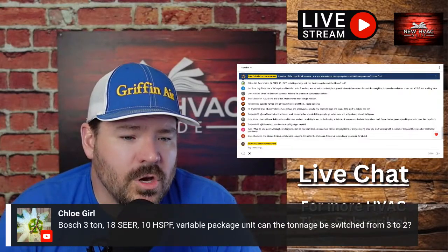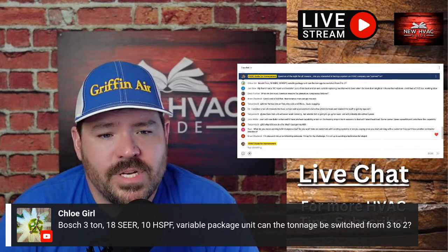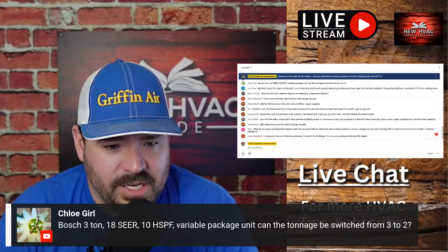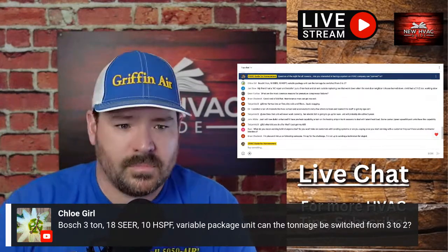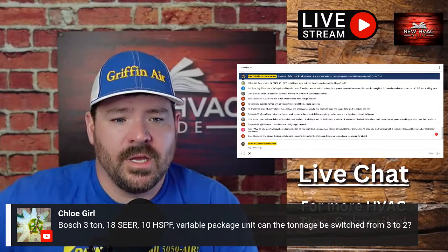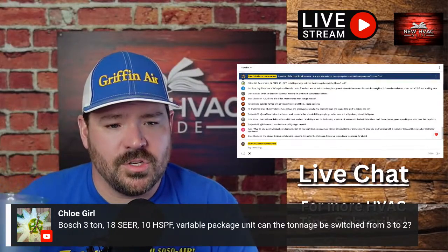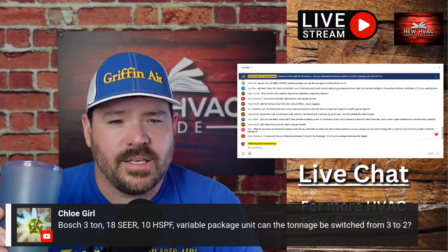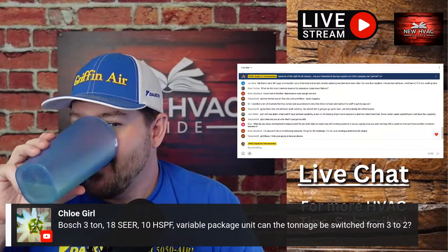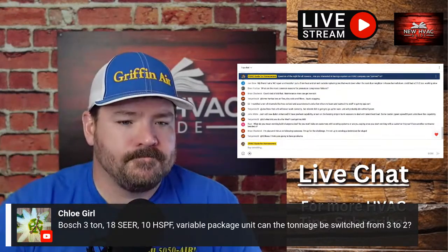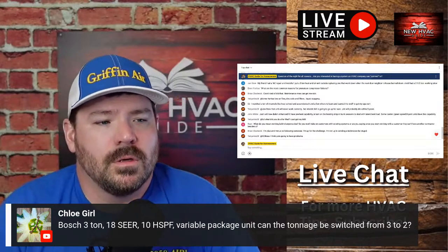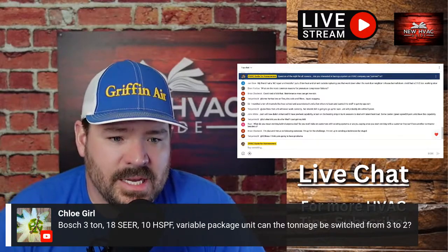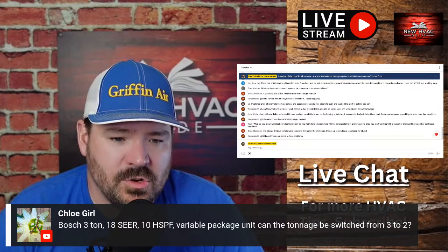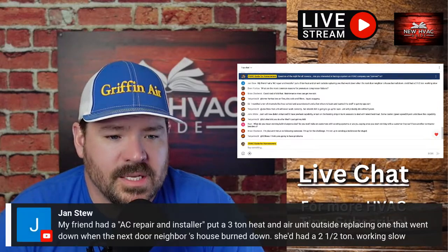Chloe, welcome to the show, I don't think I've seen your name before. Bosch 3-ton, 18 SEER, 10 HSPF variable package unit. Can the tonnage be switched from 3 to 2? I think yes, at least on the split systems that's how it is. It's just a simple dip switch, and you tell it what you want the capacity to be set at.